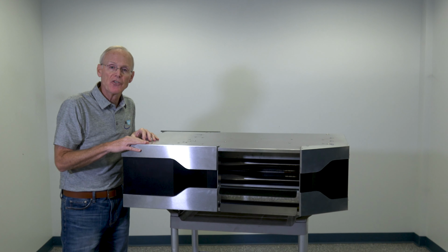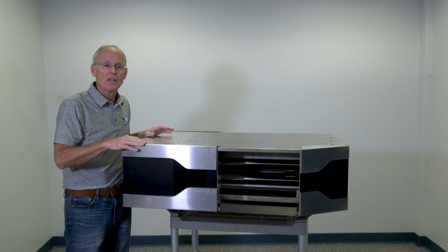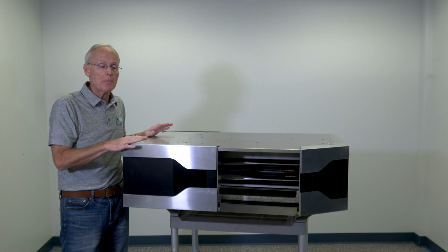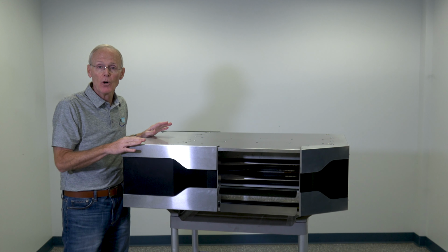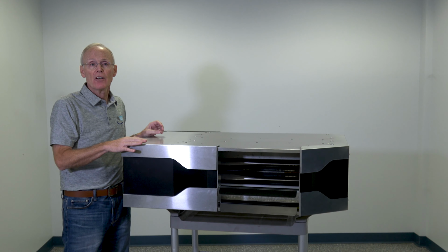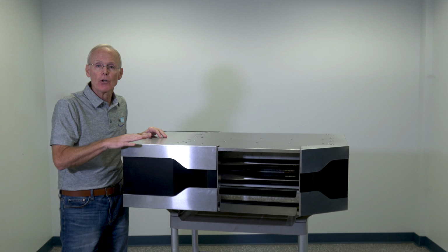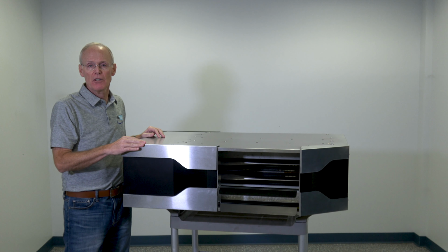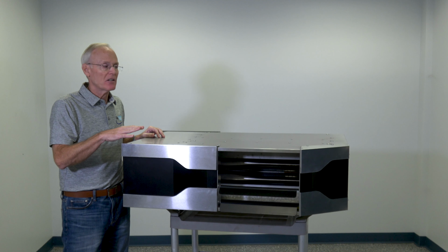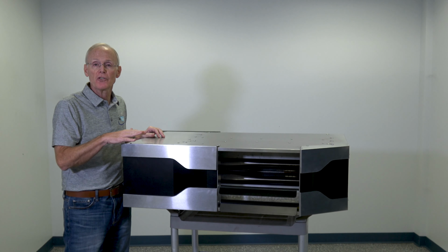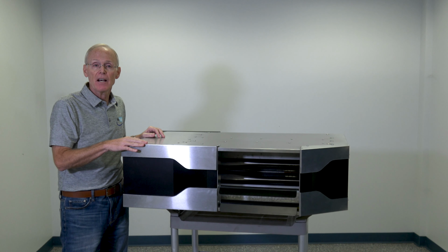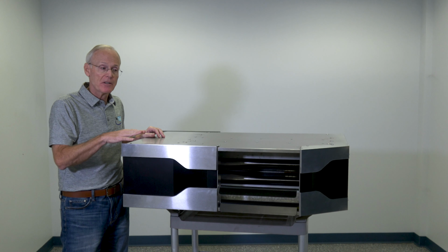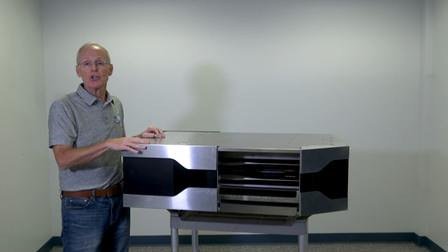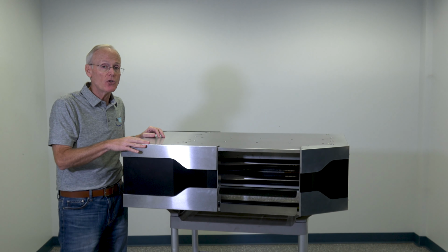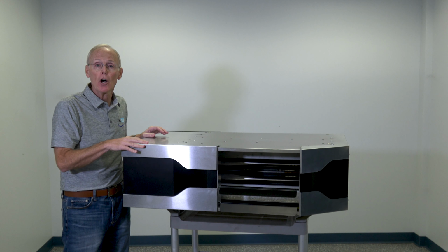Now, everybody asks what does it cost, and I will tell you that it's probably 3 to 3.5 times more than a standard unit heater. So this is not going to replace the standard 82% unit heater. This is something that is going to be maybe in high-end homes, or it's going to be in new buildings that we get specified. But the payback in a northern climate like Chicago is probably 2 to 3 years, depending on how long it operates.